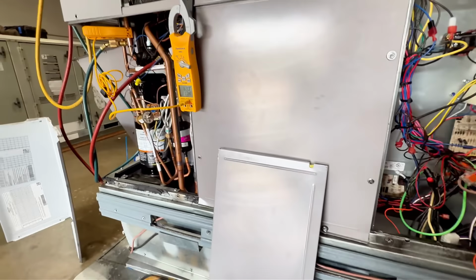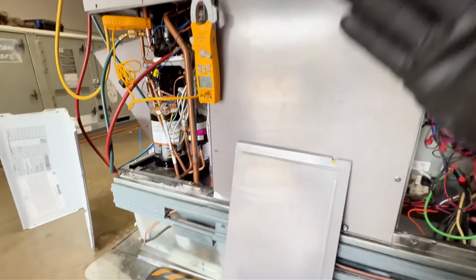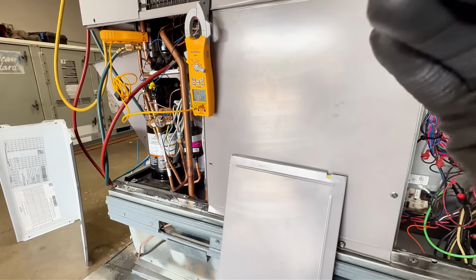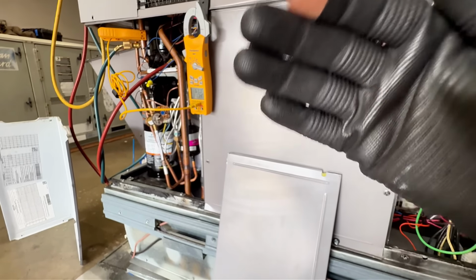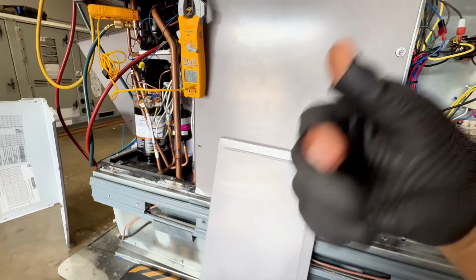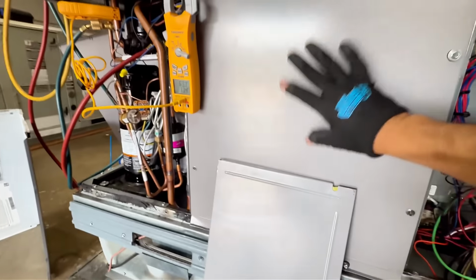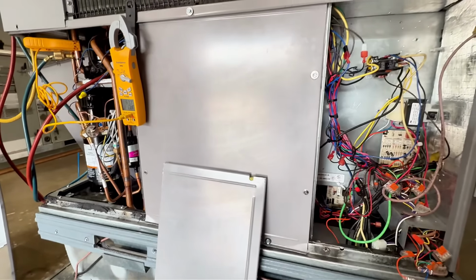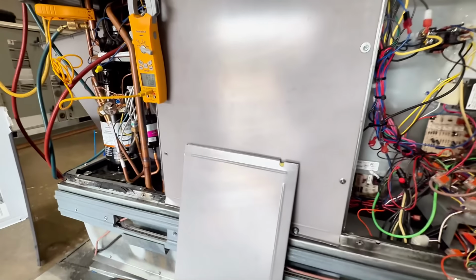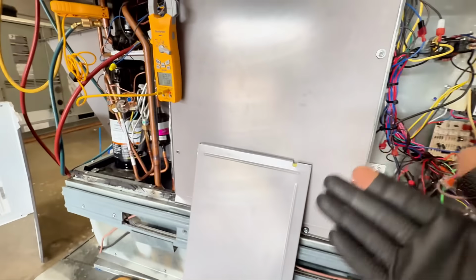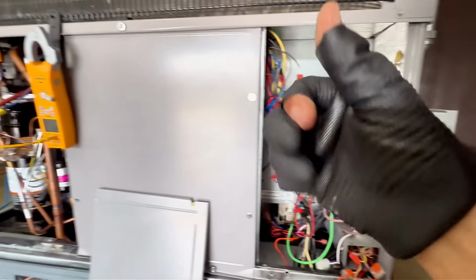And I would say this: try to come up with an acronym. For heating, I use TIP BIG FB: thermostat, inducer, pressure switch, my board, which are my safeties. What is it? TIP BIG: ignition, which is my hot surface igniter, gas valve, FB, flame rectification, and then your blower motor. TIP BIG FB. For this, it might be a different acronym. The one that I've come up with, and I'm trying to come up with another one, is TAG. Thermostat for T, A for airflow, and then G for gauging up.